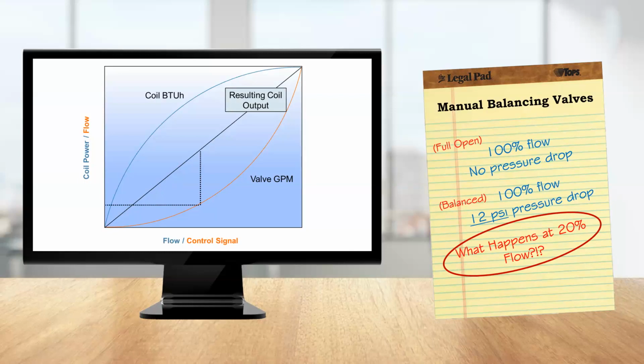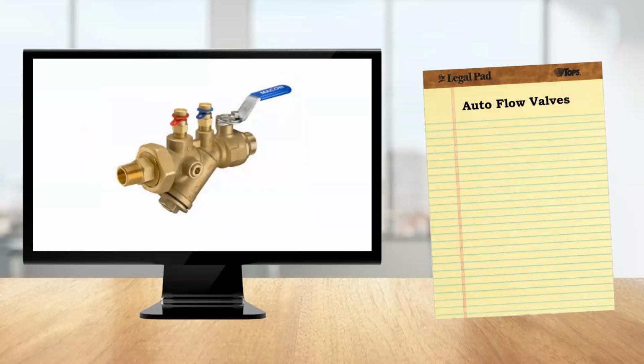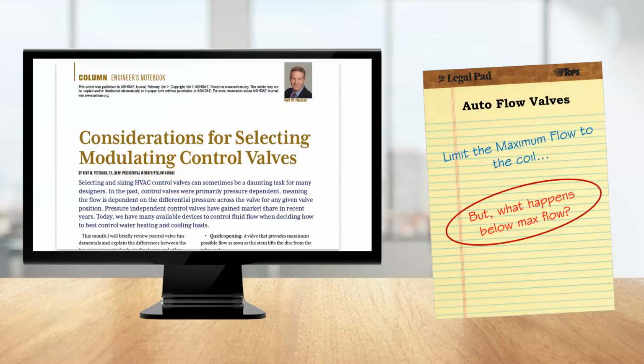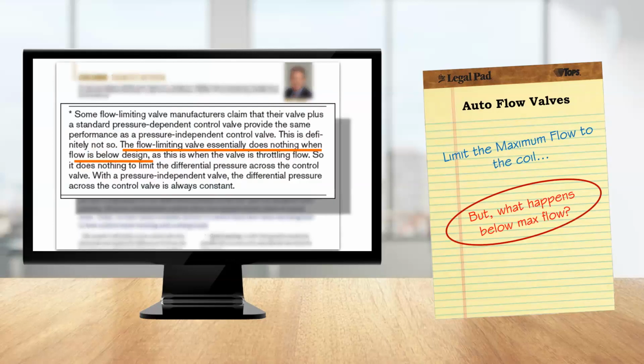But how about a flow limiting valve? Well, what happens below max flow? Essentially, a flow limiting device only caps out the maximum flow. But let's look at an article from the ASHRAE Journal of February 2017. In this article, the author states, the flow limiting valve essentially does nothing when flow is below design. So the following 3 lines are also quite excellent to support this case.